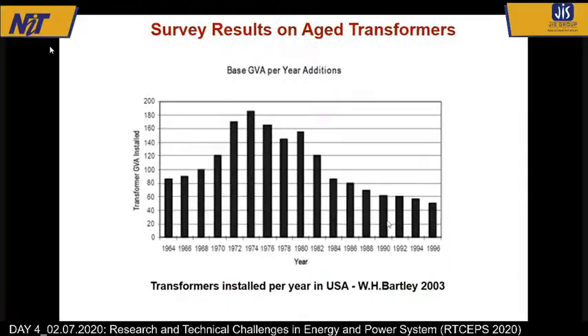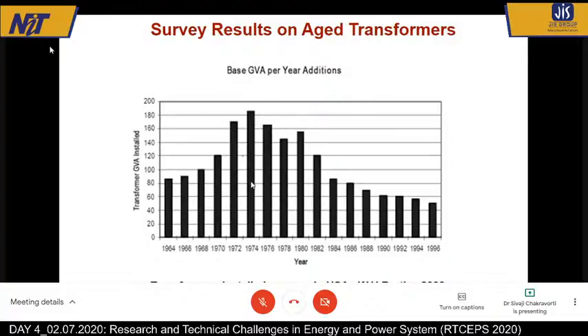The question is very simple: all these transformers which were installed in the 1970s, are they all now discarded from service? The answer is no. Probably more than 90% of them are still running, although their age will be today almost 50 years. And here I must say that every equipment has a design life. That means the designer will say what the life expectancy is. Transformers typically have a design life of 25 years or maybe 30 years. But these are way above their design life.